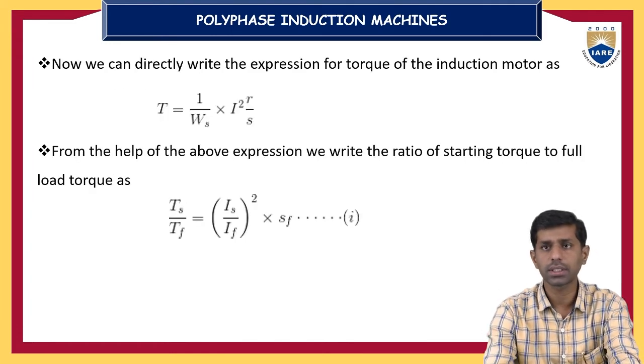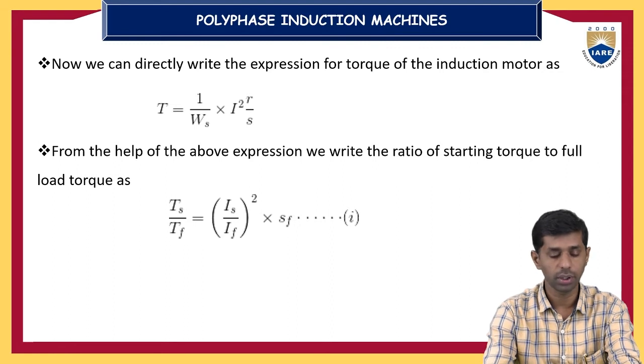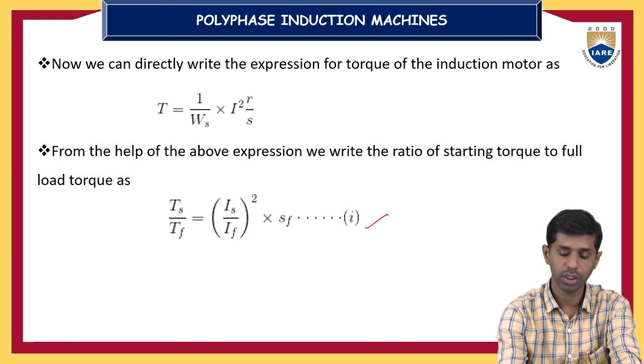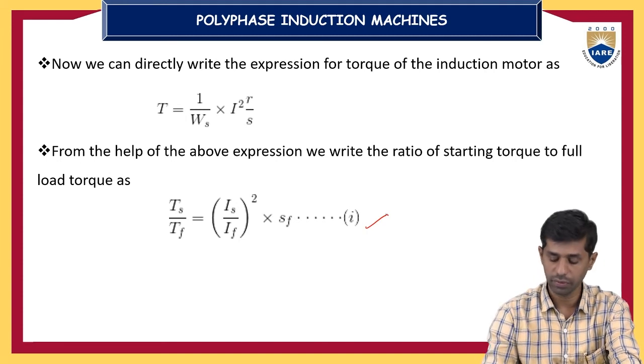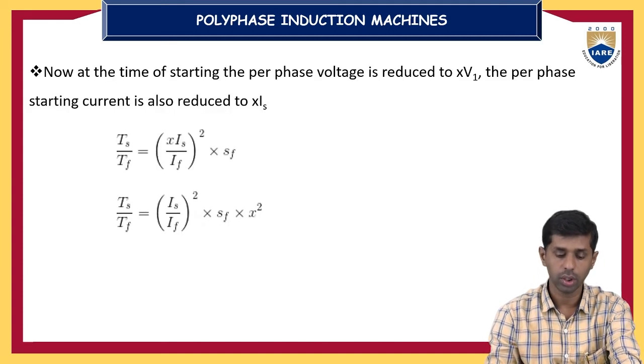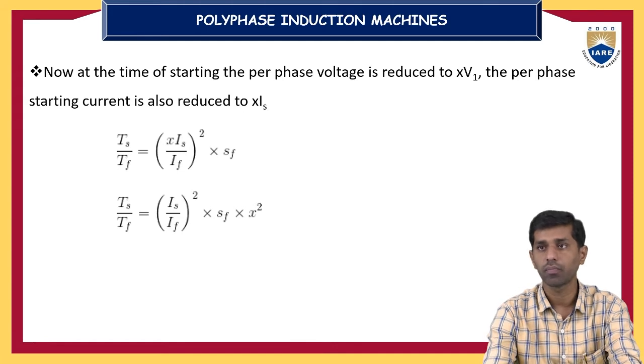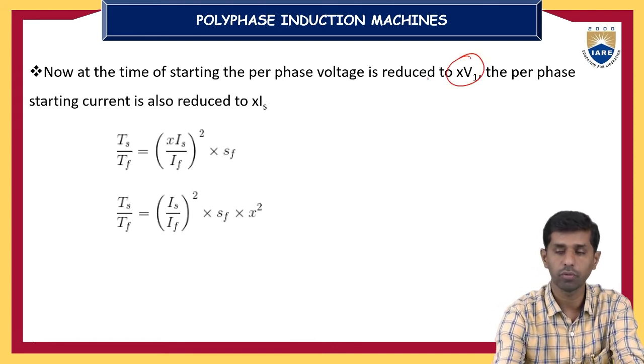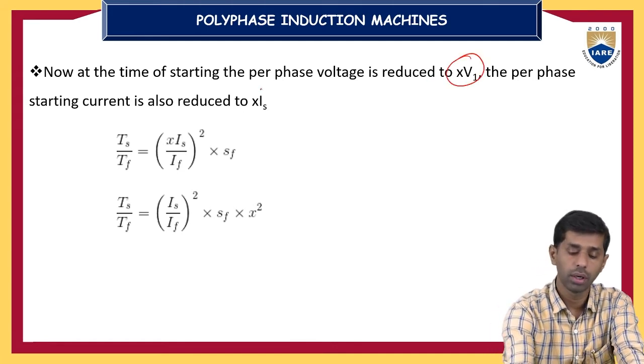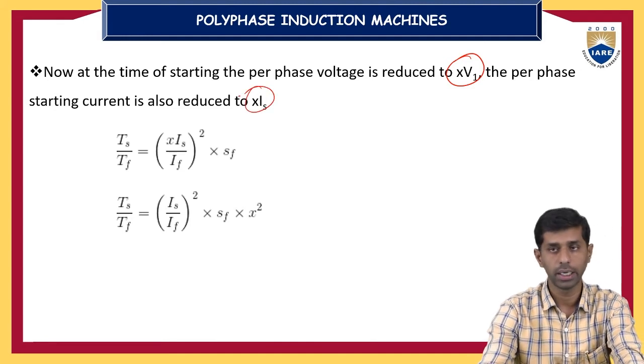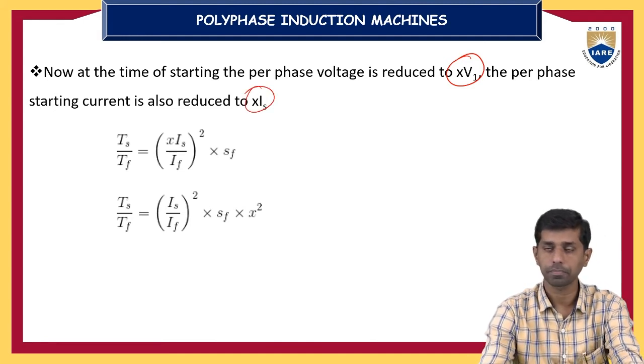And these expressions are similar to the previous cases we derived in the direct online starting as well as the resistor starting. We have a relation for the ratio of starting torque to the full load torque, this one. Equation number 1 is similar for the previous cases. So when we're talking about auto transformer starting, the voltage is reduced from V1 to X times V1, and the starting current is also reduced from Is to X times Is.